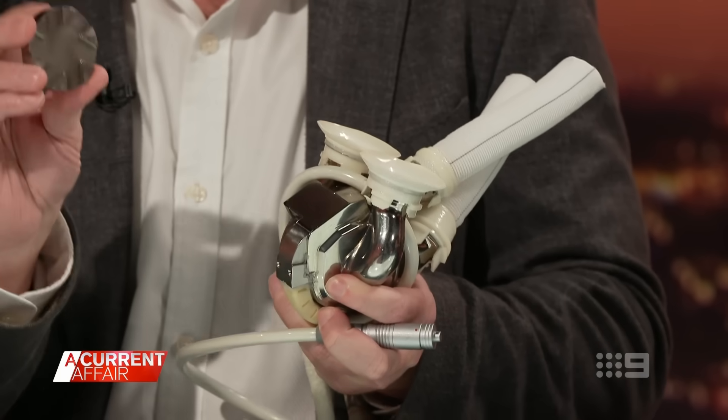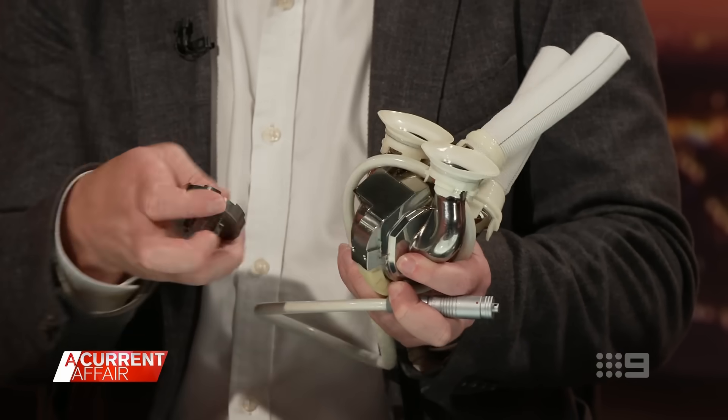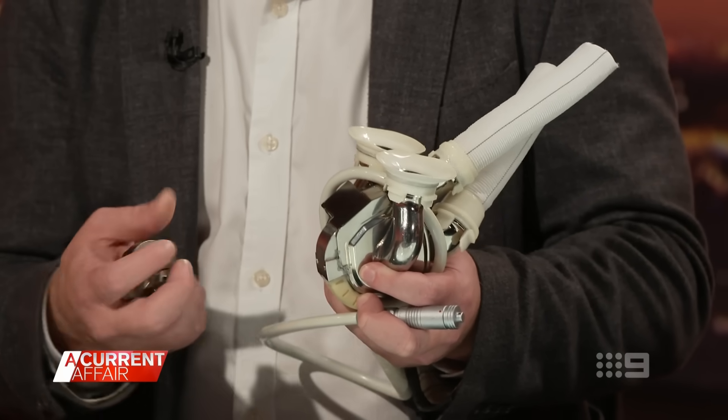So just talk me through how this works. Inside this device is a rapidly spinning disc, and this spinning disc pumps the blood to both the body and to the lungs. An artificial heart has to be extremely durable — it cannot stop. The reason this is durable is that it has three electromagnets inside that levitate that spinning disc in an electromagnetic field, just like the trains in Asia. Therefore there's no friction, no mechanical wear, no reason this device will stop if we power it. We can actually recreate a heartbeat by turning the speed up and down once a second, so the outflow will increase once a second, just like a heartbeat.